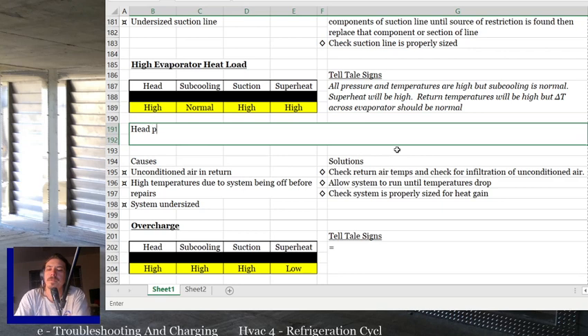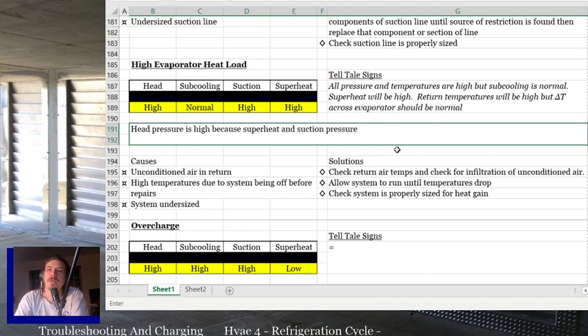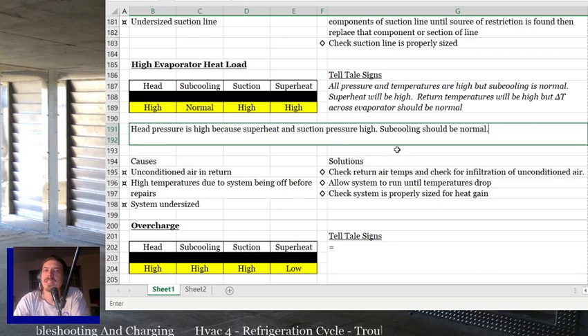So head pressure is high because superheat and suction pressure are high. So basically, the fact that we're picking up so much heat is what's driving the system pressures to be high. Because the suction pressure and the superheat are high since we're picking up so much heat, the head pressure is going to be high. Subcooling should be normal. Delta T should be normal. Subcooling might be a little bit low on a TXV if it's overfeeding refrigerant to try and take care of the issue, but it should be pretty close to normal. It might be supposed to be 10 and you're reading 7 or something like that. Again, plus or minus 3, don't start freaking out. But really the reason everything's high is just because you're picking up a lot of heat in the evaporator.